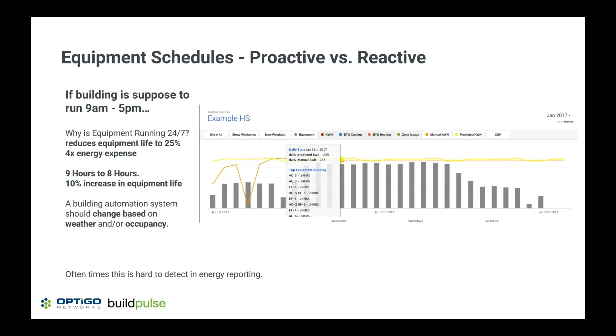If you look at your equipment lifetime, running equipment 24/7 basically reduces its lifetime to a quarter of its potential operation. Even shaving just 1 hour off your equipment runtime can be potentially a 10% increase in equipment lifetime. So even though a lot of people talk about advanced algorithms, very basic schedule discipline can have a huge impact on extending equipment lifetime.